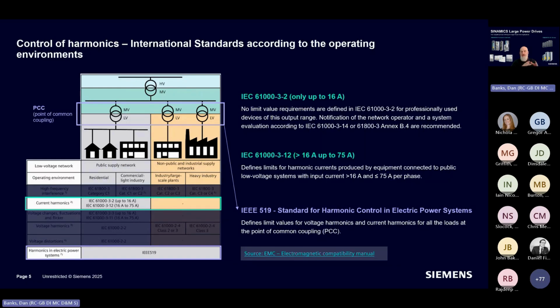These are the sorts of standards the world has defined for us. There are IEC standards and IEEE standards referring to harmonics, both for product standards and for grids. But in the UK we tend to worry more about a standard called G5/5, formerly G5/4, which is a standard rather than a regulation - so it's not the law. No one's going to sue you if you don't comply with it. But typically there'll be some clause in your contract with your power supply company requiring your site to be compliant with this standard.